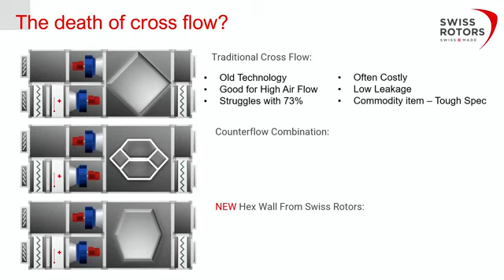Everybody has a Crossflow heat exchanger in our industry, so really making a tight specification with a Crossflow is going to be very tough. Then there's the newer type of combi counterflows that you get, which is a recent technology, but it has a complex factory build, so you have to assemble those separate components together when they arrive in the factory. And I know that from a labor perspective, that can be restrictive, so it takes a lot longer to assemble these types of products together. They're good for high airflow, similar to the HexWall, and they also possess a very low leakage as well, the same as the HexWall. They have a great level of efficiency with a combi counterflow, and they can create a good spec, but it's not unbeatable.